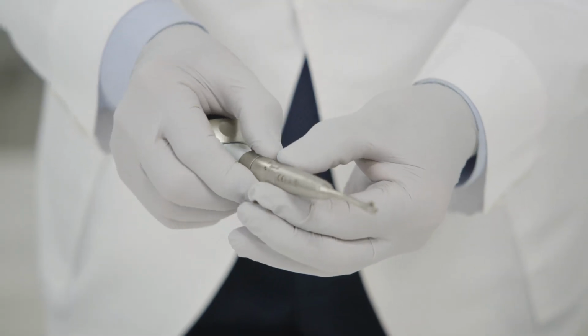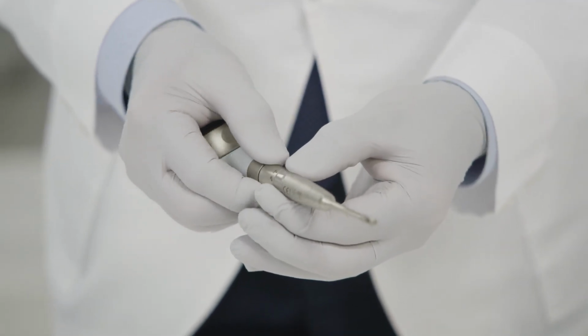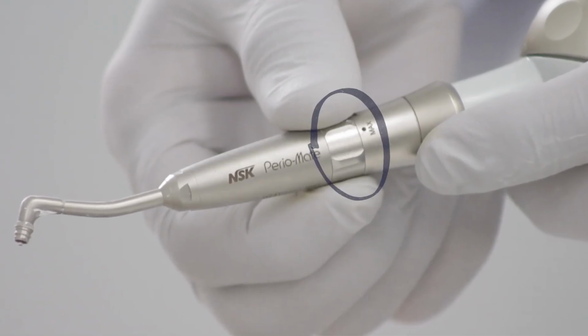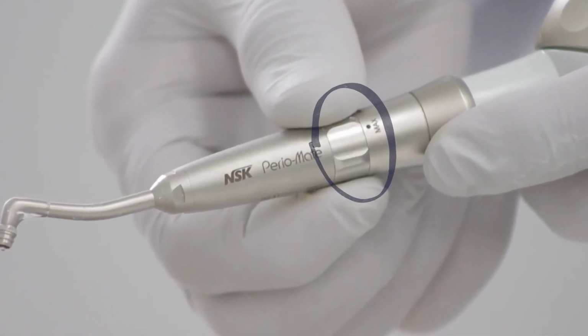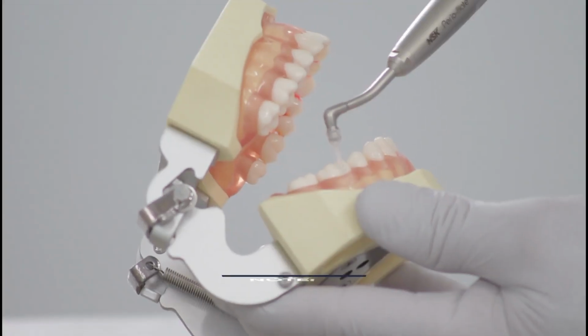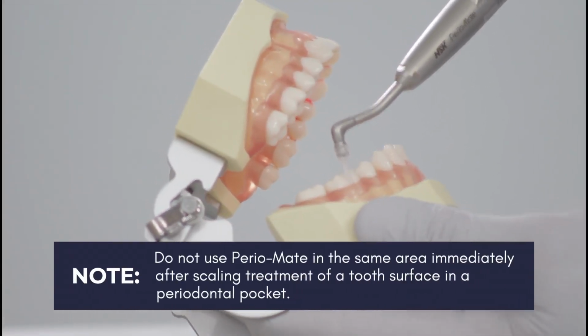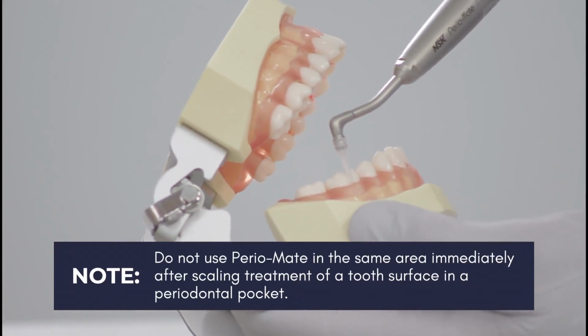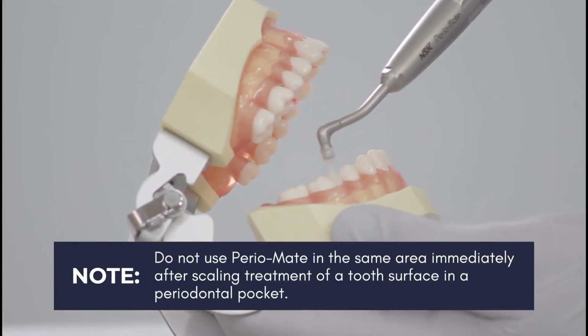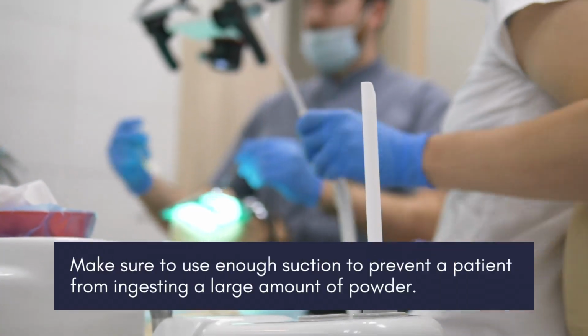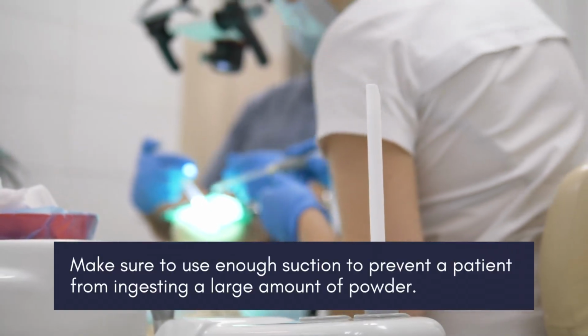The powder spray volume can be adjusted using the flow adjustment ring. Start by setting it to minimum and then adjust it according to the application or patient's conditions. Note: do not use Perio-Mate in the same area immediately after scaling treatment of a tooth surface in a periodontal pocket. Make sure to use enough suction to prevent a patient from ingesting a large amount of powder.